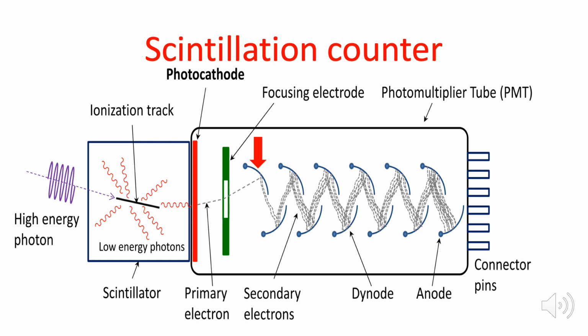The problem with the scintillator is that the amount of light energy that it produces is not as much as the amount of radiation. Remember, the amount of radiation will reflect the concentration of the antigen and antibody. So the light that must be detected by the scintillation counter should match the energy of that of the radiation. So this instrument must come up with a way in order to match the amount of light energy to the amount of radiation that is coming from the Radioimmunoassay test setup. That's why, as you can see in the picture, once the photons are released from the scintillator, they will come in contact with the photomultiplier. So look for the photomultiplier tube name in the photo and take a look at the portion of the instrument that is labeled such.